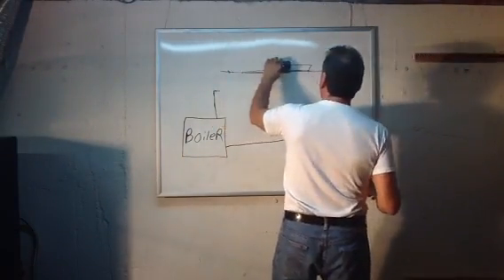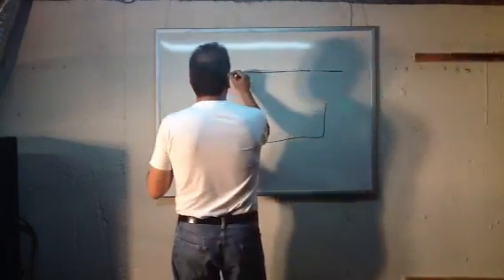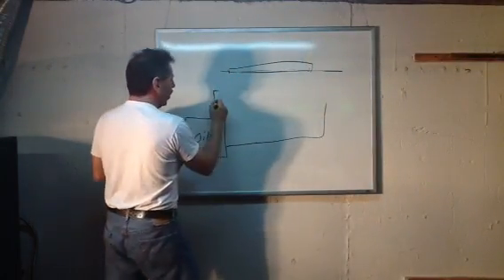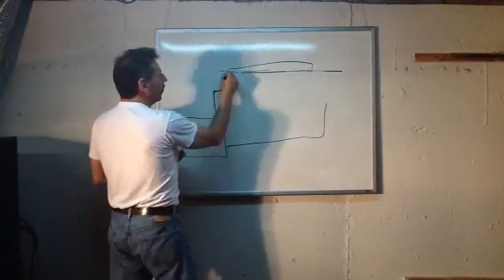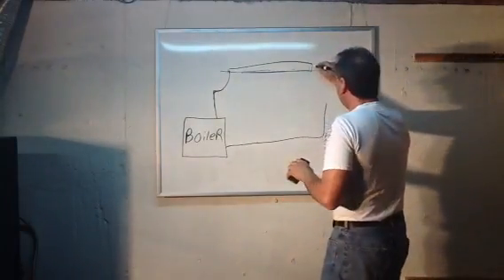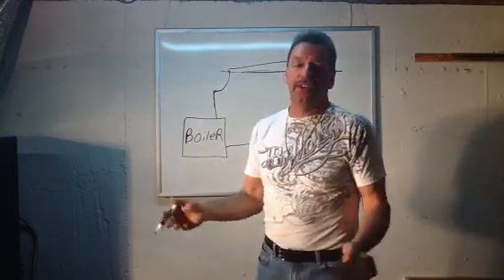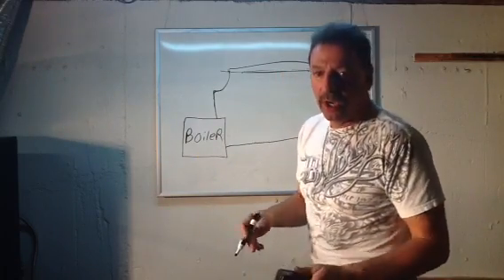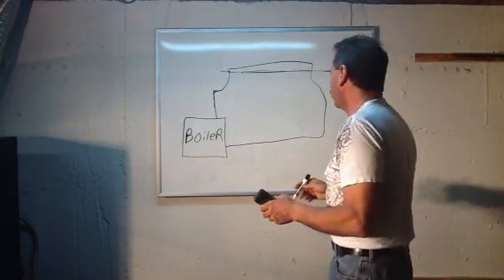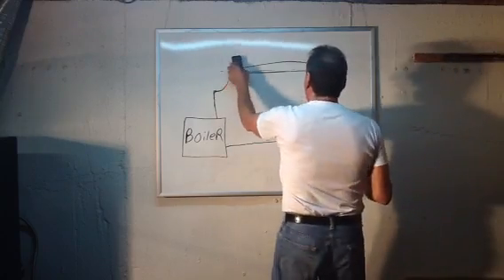Now what you have is 90% of your 180-degree water traveling by the baseboard, or maybe only 10% of it going up. That does not work. Baseboard needs 100% of the water going through it all the time. 100% of the water has to go in, travel through it, and return back out of it. That's the only way you're going to get your 600 BTUs per foot which was designed to heat the room.